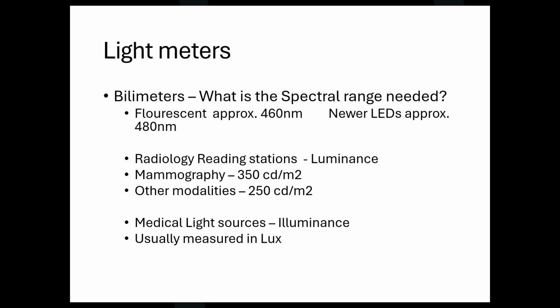So the newer, which most everybody has gone to, are LEDs. Look what range that runs in, or what they typically are, 480 nanometers in that spectrum. Look at your bilimeter when you get back. Look at your bili light. So if most of the old ones go 450 to 470, I'm not getting an accurate reading now on my nice little new LED bili lights that I'm using. Okay.